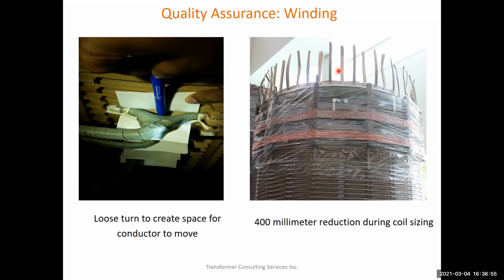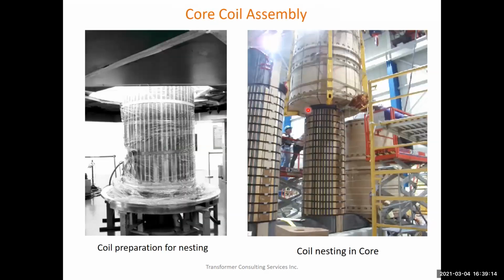When you are reducing the winding by 400 millimeters, that means mechanically you are loosening the winding. When you are mechanically loosening the winding, you are compromising the quality of the winding, which can compromise the quality of the transformer in the long run. So now on the left-hand side, you create those coils. Then on the right-hand side, you nest those coils into the core.